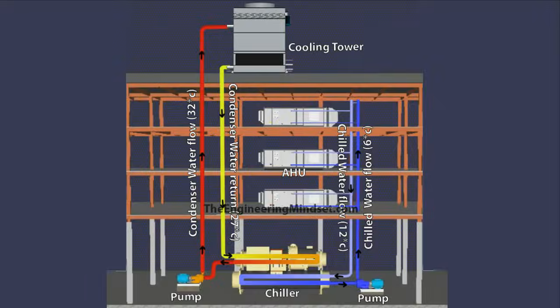and much more compact. And the reason that's really important is because, as you know from the layout here of the chiller, we're picking up about 6 degrees Celsius on the chilled water as it's going up and picking up the heat from the building. We've got to take that heat from that circuit and move that over to the condenser circuit. Now heat flows from hot to cold, so in order for us to extract the heat out of the chilled water loop and move it into the condenser water loop, we're going to have to make sure that the refrigerant that carries over there is entering the condenser at a higher temperature than this return water. So you can see it's coming back from the cooling tower at about 27 degrees Celsius. That means the refrigerant, in order for the condenser to reject heat, the refrigerant coming into the condenser has to be hotter or at a higher temperature than 27 degrees Celsius in this example.